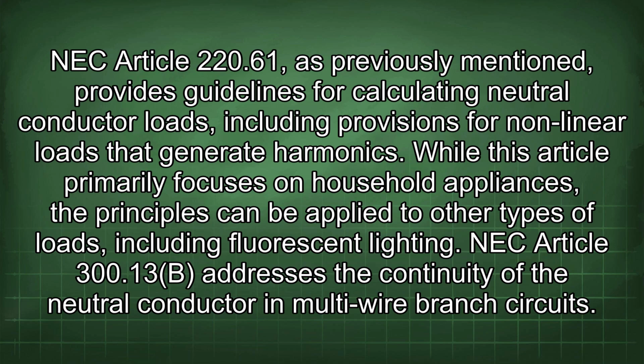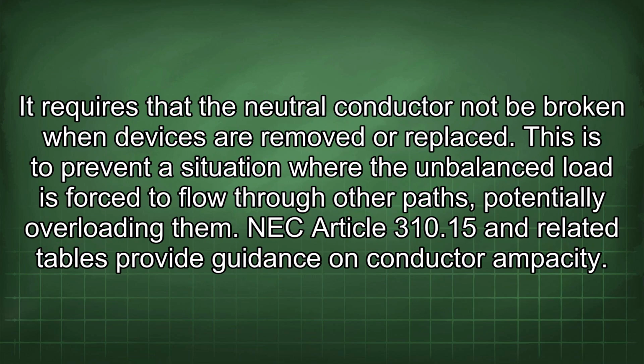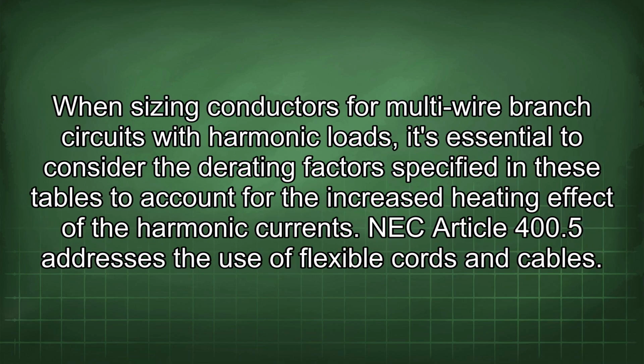fluorescent lighting. NEC Article 300.13(B) addresses the continuity of the neutral conductor in multi-wire branch circuits. It requires that the neutral conductor not be broken when devices are removed or replaced. This is to prevent a situation where the unbalanced load is forced to flow through other paths, potentially overloading them. NEC Article 310.15 and related tables provide guidance on conductor ampacity. When sizing conductors for multi-wire branch circuits with harmonic loads, it's essential to consider the derating factors specified in these tables to account for the increased heating effect of the harmonic currents.